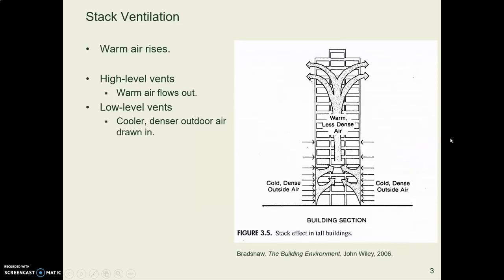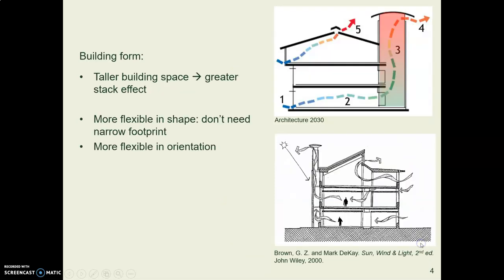Stack ventilation is based on the principle that warm air rises. In a building cooled by stack ventilation, you'll have a tall structure — a tower, a stack, a stairwell, something tall — with openings at the top so that warm air can flow out. That creates a partial suction and pulls cool air in from the bottom. The taller the space, the greater the stack effect. You don't need to worry as much about the shape of the building or what direction it's oriented, because it's all about the stack and the warm air rising.